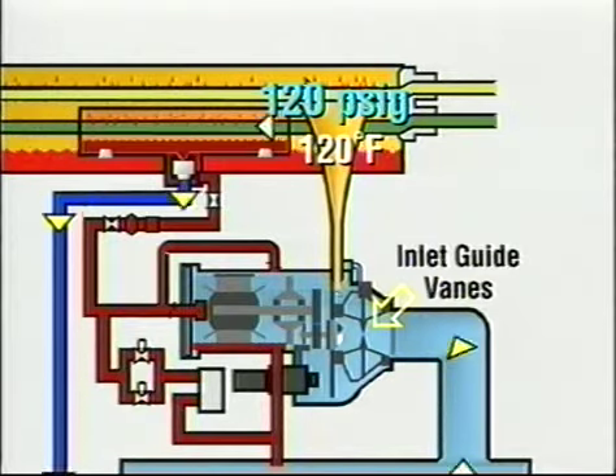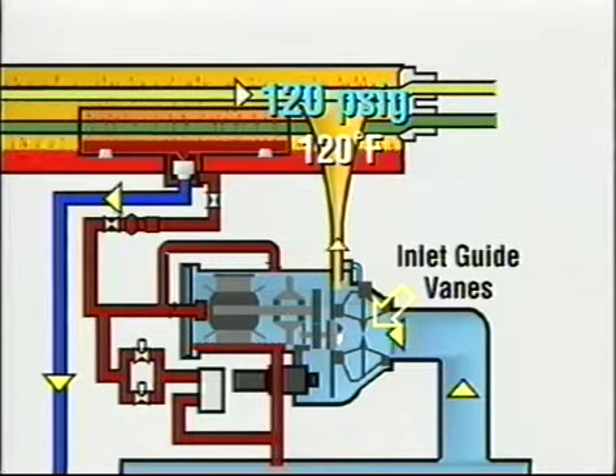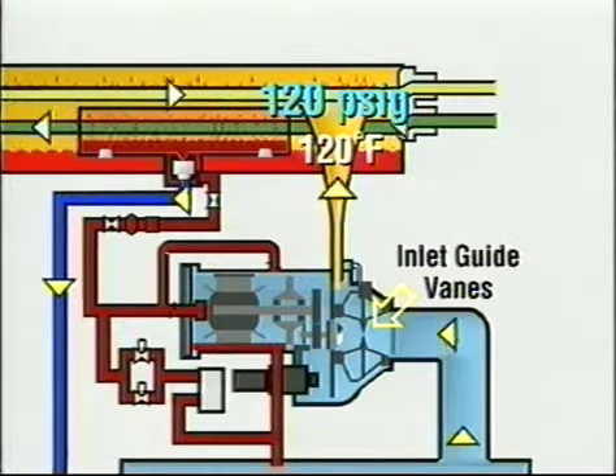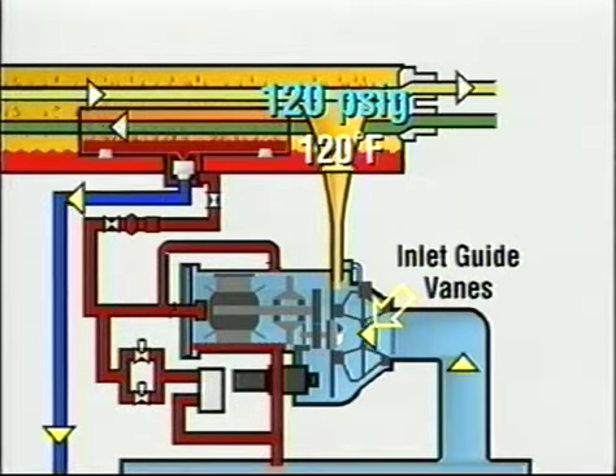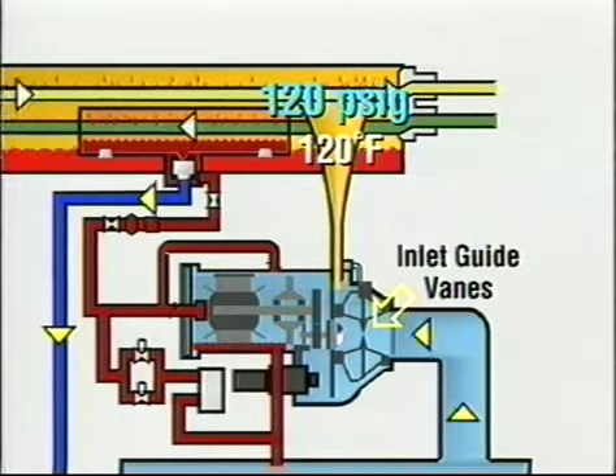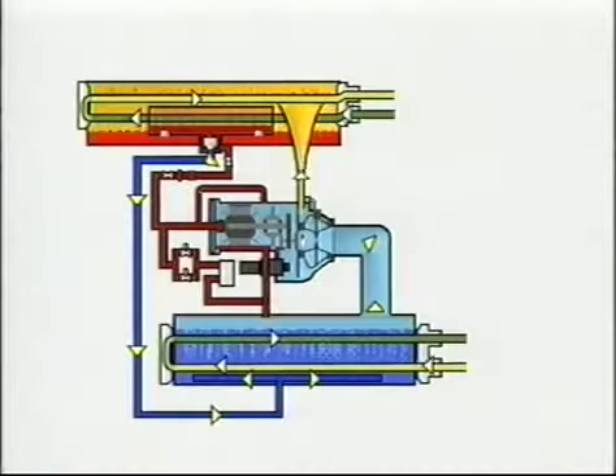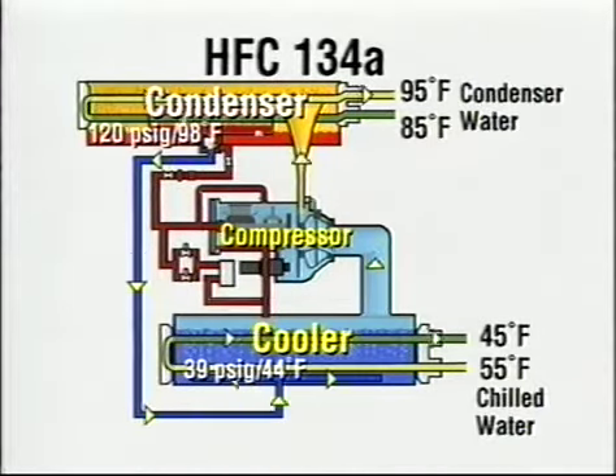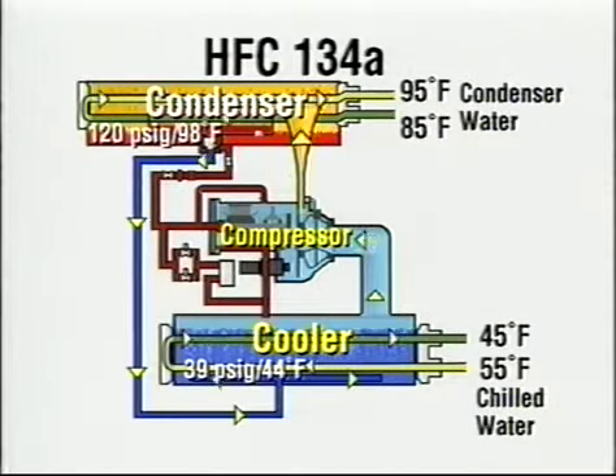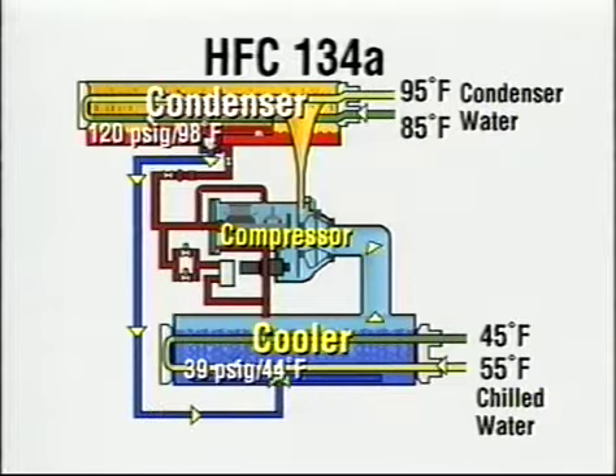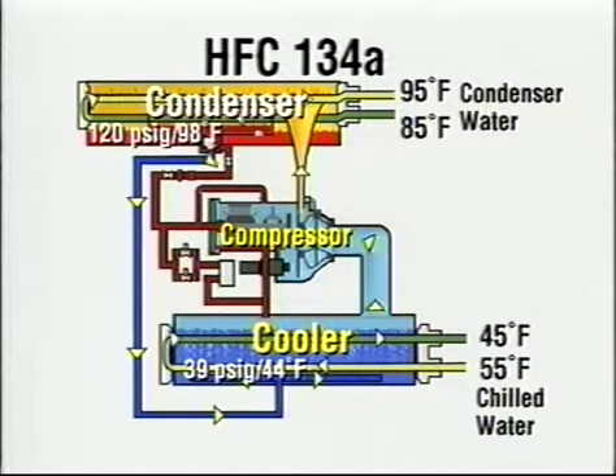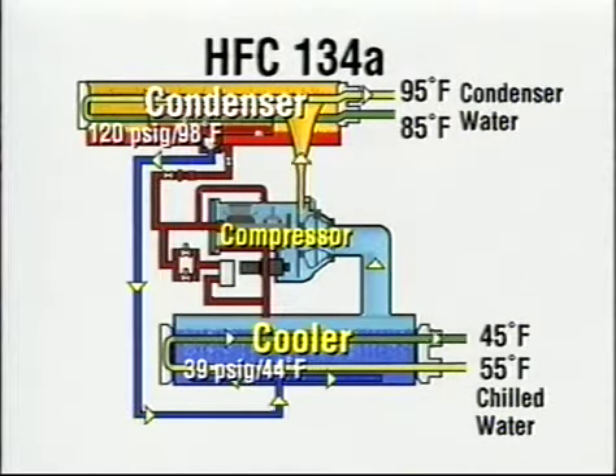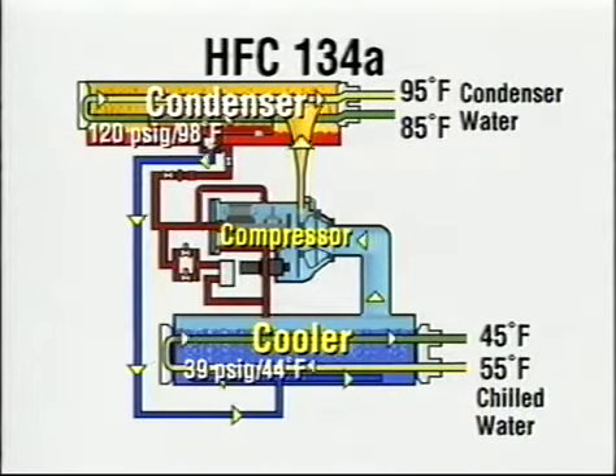The compression process adds heat to the compressed vapor, raising its temperature to about 120 degrees Fahrenheit. This temperature will change based on load, refrigerant charge, or non-condensables in the machine. The water-cooled condenser is a shell and tube heat exchanger similar to the evaporator. Cooling tower water at 85 degrees Fahrenheit flows through the tubes, removing heat from the refrigerant vapor, causing it to condense on the outside of the tubes. The saturated condensing temperature of the refrigerant vapor is 98 degrees Fahrenheit, corresponding to the pressure of 120 psig.